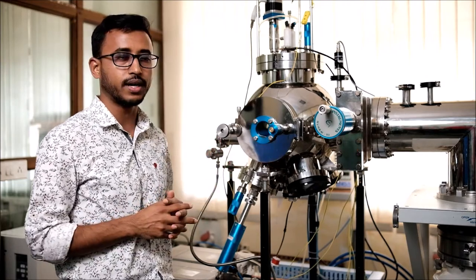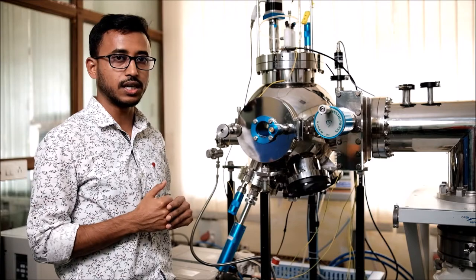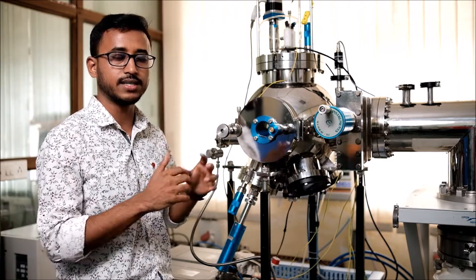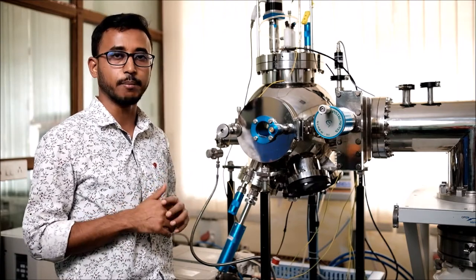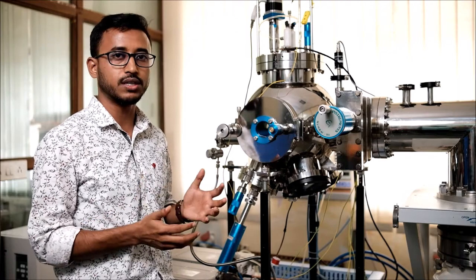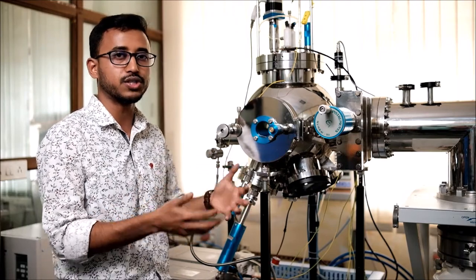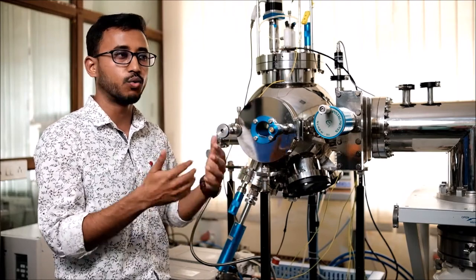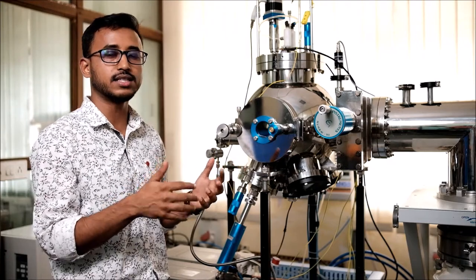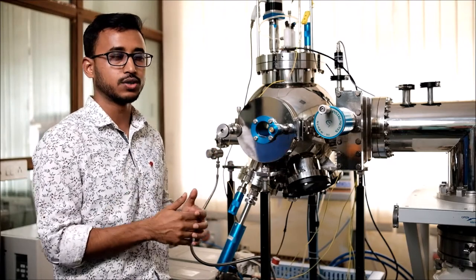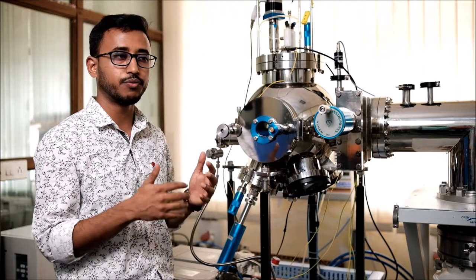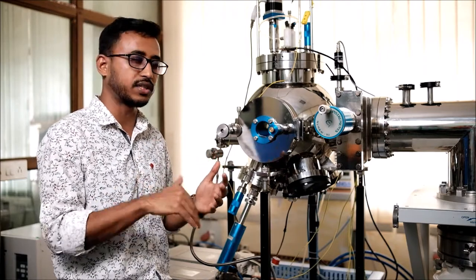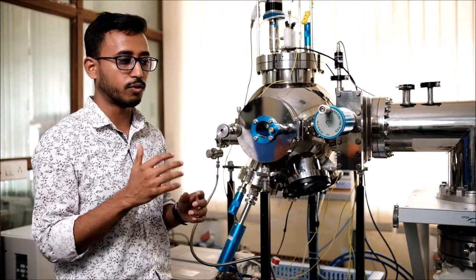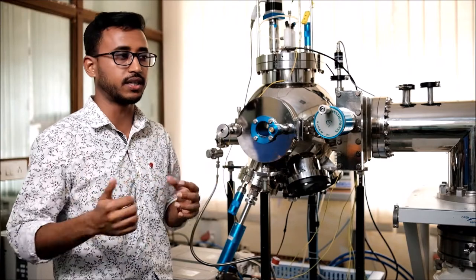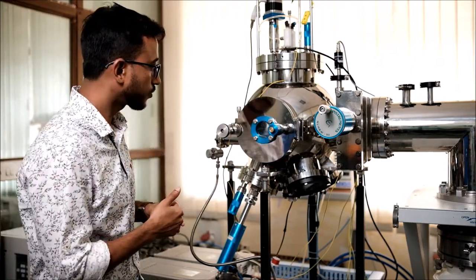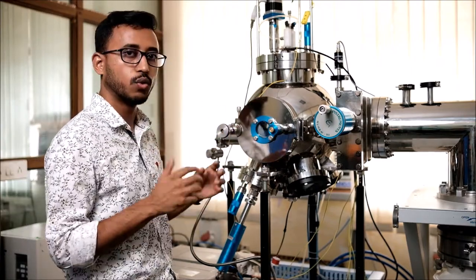This actually operates on the crystal operation. It has its natural frequency of 6 megahertz. Whenever we deposit, the material also deposits onto the crystal and its weight gets increased, and thus its natural frequency gets reduced. So by calculating its natural frequency before and after the deposition, we can correlate this parameter into the thickness of the system. With the help of a software, we do this.